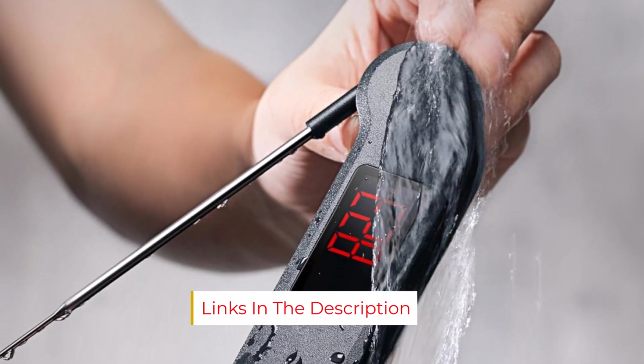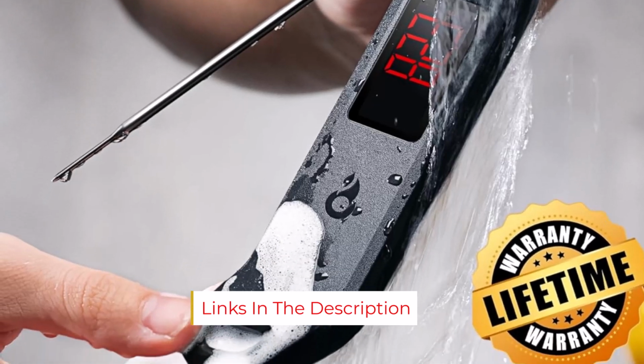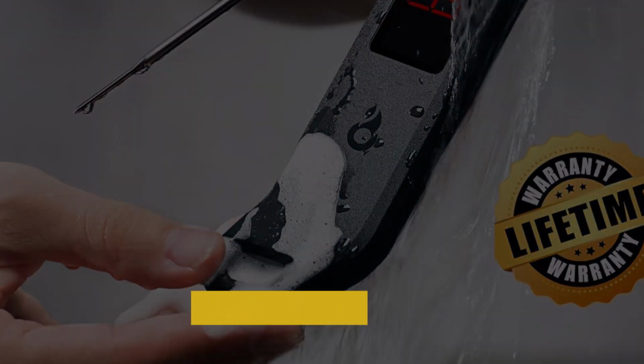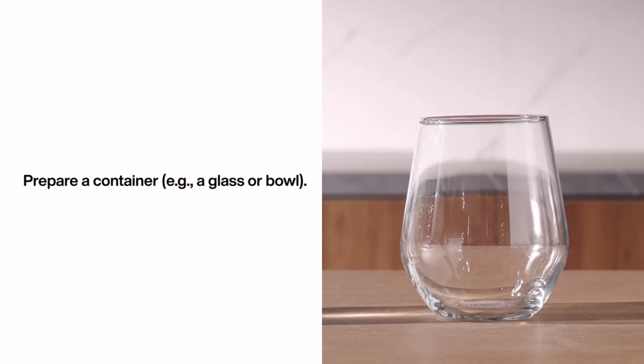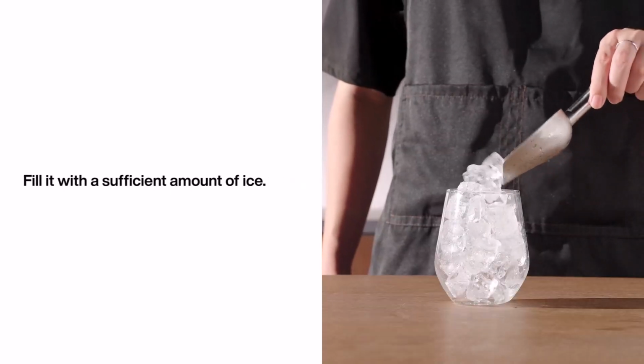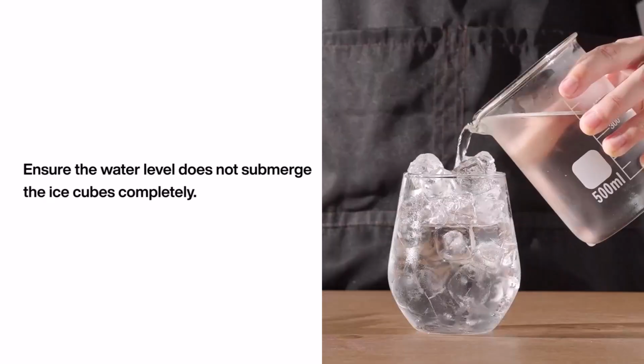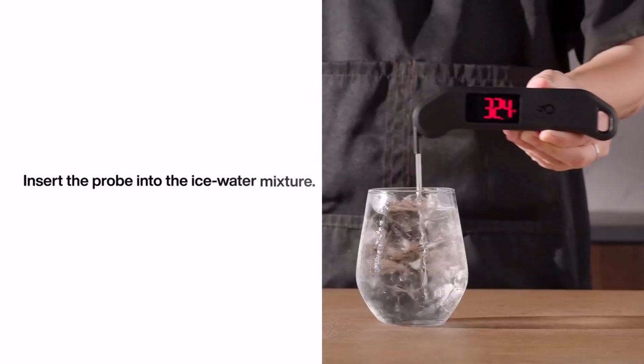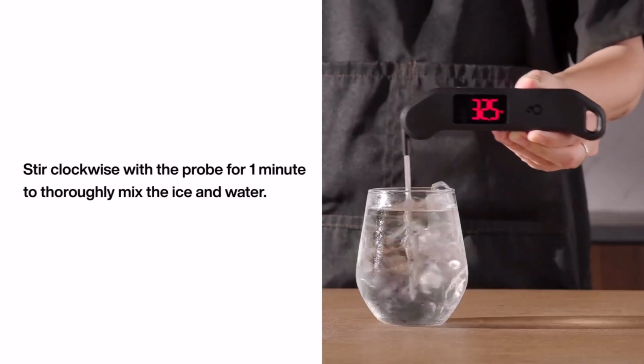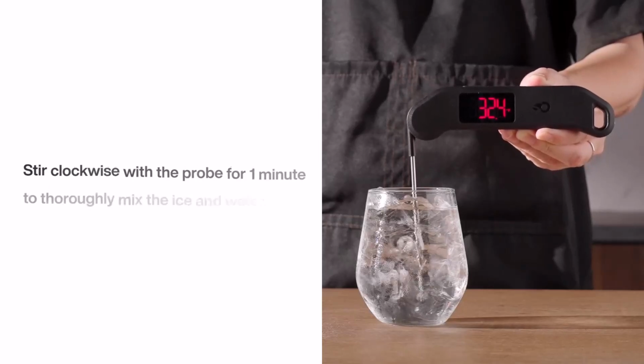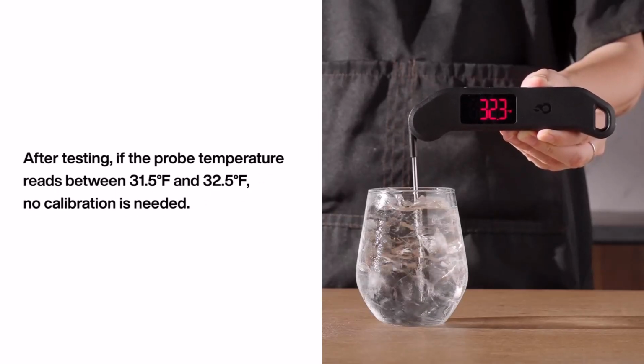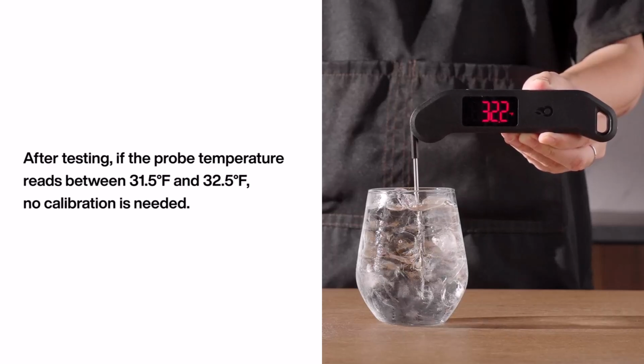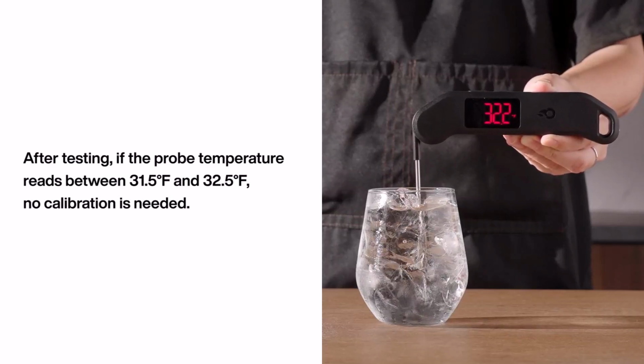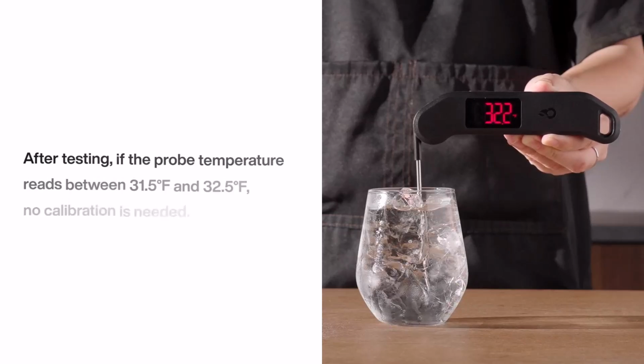Its highest response time was 6.7 seconds, its lowest was 2 seconds, and its average was 3.35 seconds, all of which are above the stated 1 second. The case is rectangular with smooth angles, but those angles still leave some edges that can dig into your hand, so while I wouldn't call this uncomfortable to hold, I wouldn't call it comfortable either. The red-on-black LED was easy to read even in limited lighting, and the display rotates 180 degrees to align with the case's direction, so you won't have to worry about reading it upside down. The 4.3-inch probe is fairly standard length, which allows you to keep your hands away from the heat, unless you're working directly over an open burner or grill.